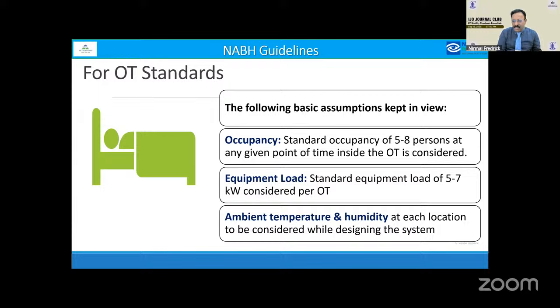The standard occupancy is one patient, 5 to 8 in the surgical team at any given point of time. Unfortunately, many of our theaters have at least double the number of occupants in the theater at any point of time. Standard equipment load of 5 to 7 kilowatts, which includes the operation microscope, the Boyle's apparatus, and the lighting systems, and ambient temperature and humidity at each location to be considered while designing the system.